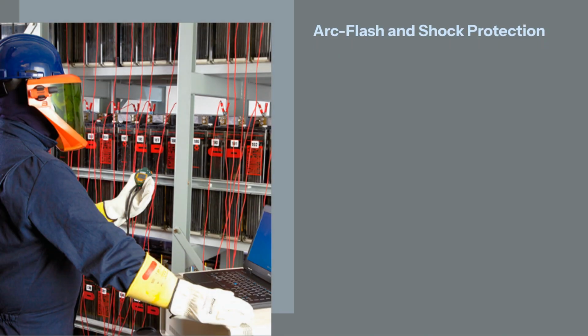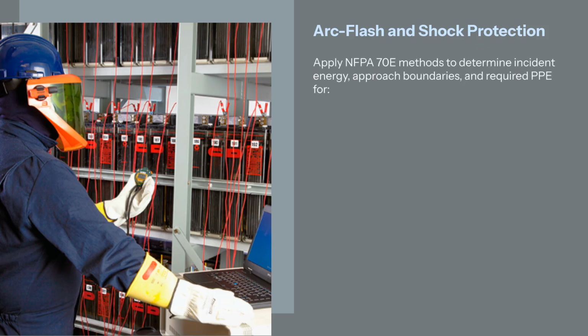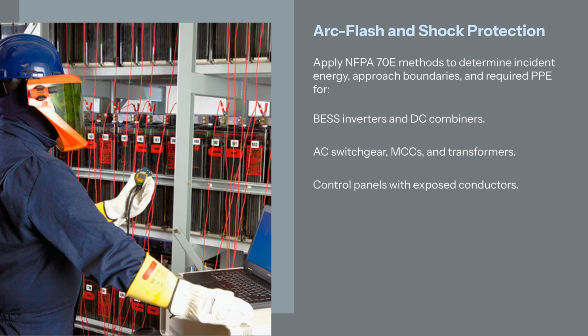When working on battery systems, we need to address arc flash and electrical shock hazards. Apply NFPA 70E methods to determine incident energy, approach boundaries, and required PPE for battery energy storage system inverters and DC combiners, AC switchgear, motor control centers, and transformers. Control panels with exposed conductors.